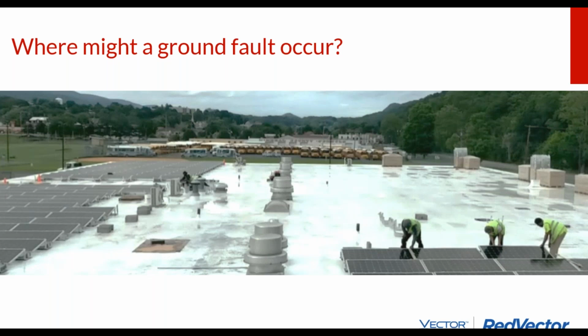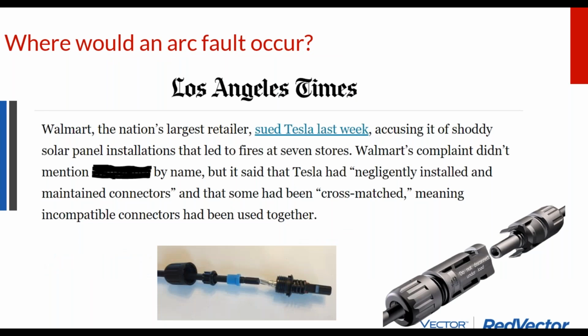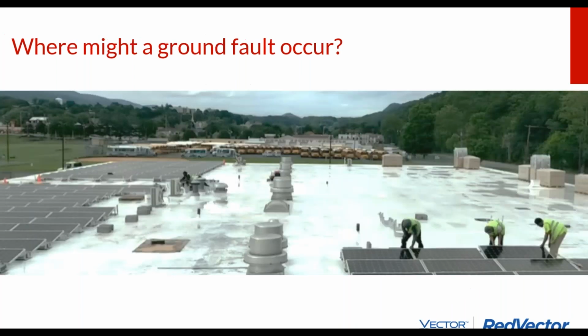It used to be back in the solar industry, we didn't worry about arc faults. The arc fault detection is harder and more nuanced. You can imagine, detecting little changes in voltage caused by this tiny connector. That's a lot less dramatic than a ground fault. So arc fault detection has only come on of late. Now inverters are equipped with arc fault detection, but the inverters 10 years ago were not. So the solar industry 10 years ago had this reputation of being bulletproof, never had an issue, when in reality, some of these arrays might have minor arc faults going on, that are not an issue today, but could be an issue down the road.